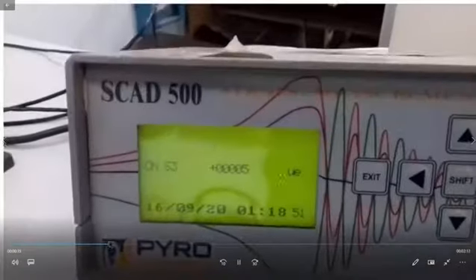The strain gauge is connected to a strain indicator which directly gives you strain in microstrains, and now it is showing about 6 microstrains.